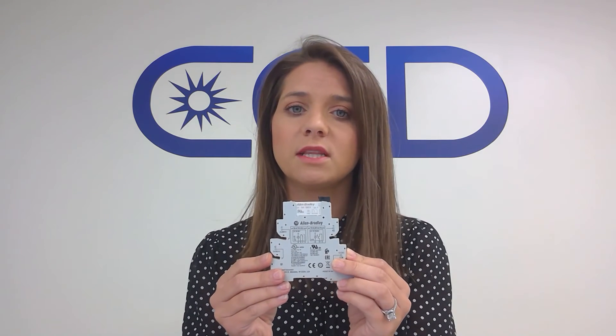We also have additional control input options. There's a 24-volt AC-DC option as well as a new wide range option, which ranges from 24-volt to 240-volt AC-DC — a great way to decrease your stock. There's also built-in leakage current suppression, as well as a few new accessories, including a push-in terminal doubler and a wiring connection adapter.